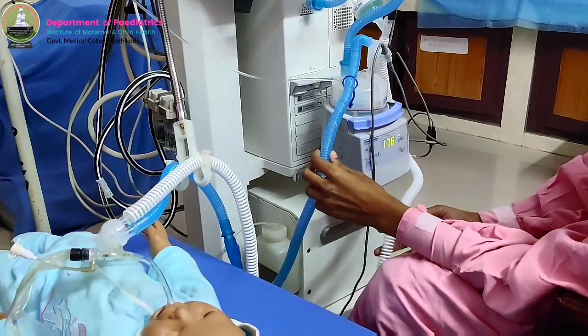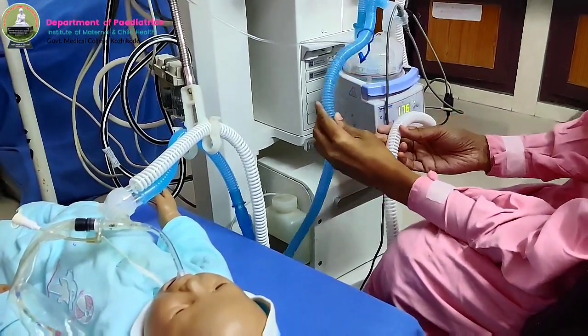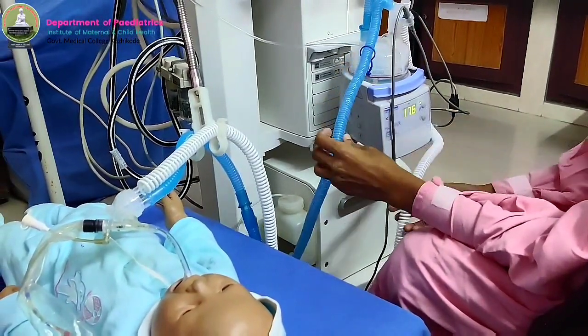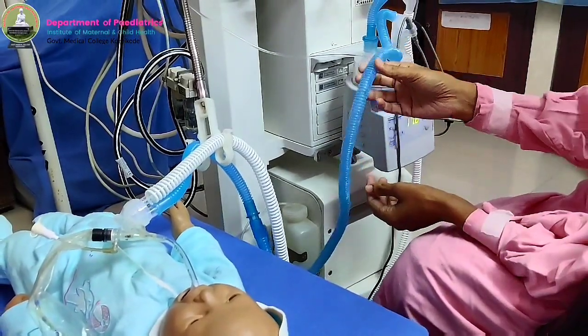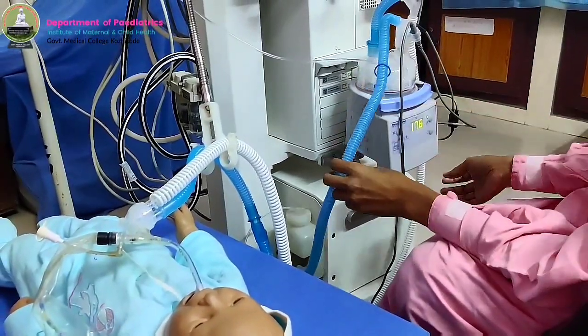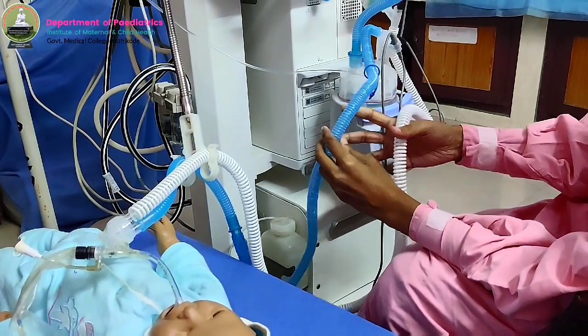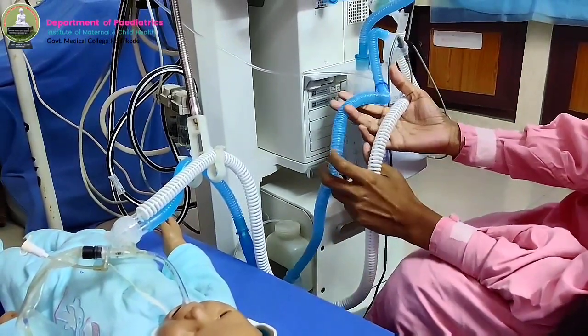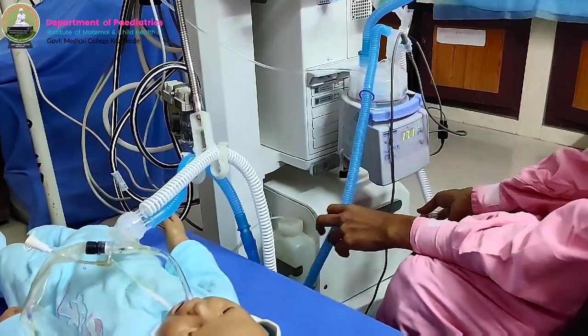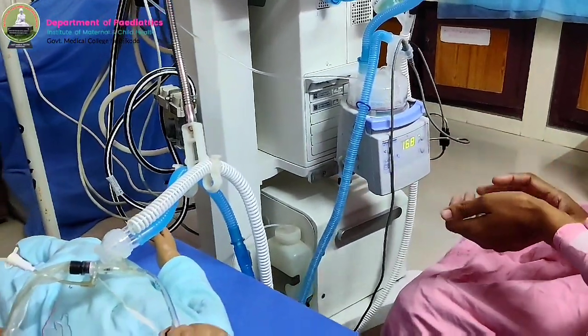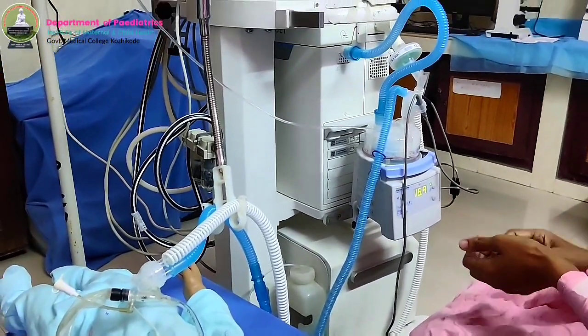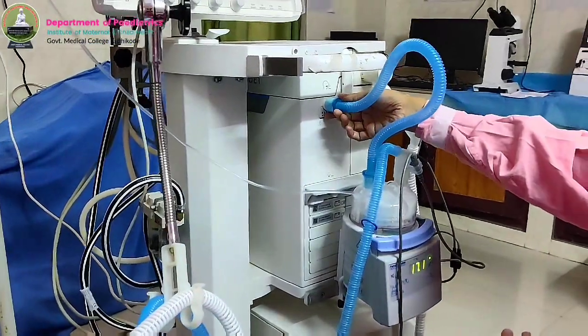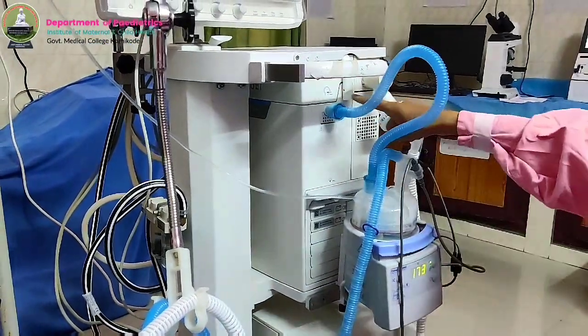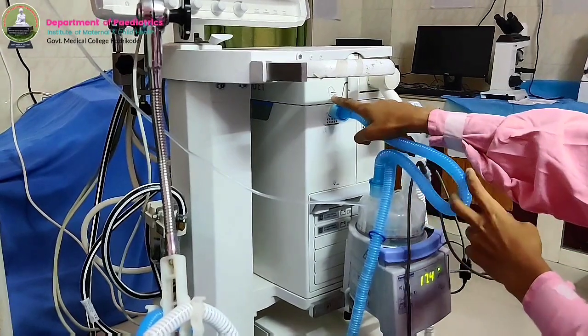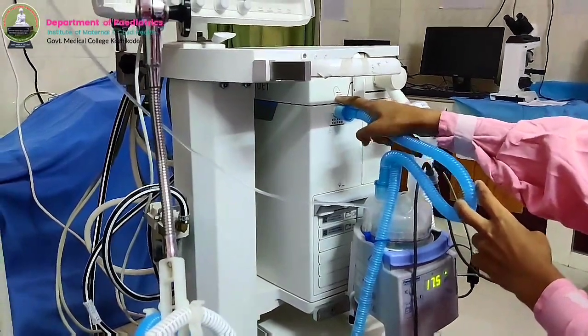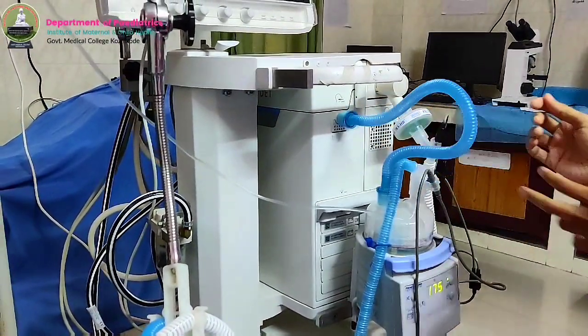As I already mentioned, there are 3 types: dual heated or double heated ventilator circuit, circuit with inspiratory limb alone heated, and circuit where there is no heating of the inspiratory or expiratory limbs. First, you should know how to connect the ventilator circuits. Always start from the inspiratory end. In this ventilator, you can see the marking showing the inspiratory end. So always start from the inspiratory end.